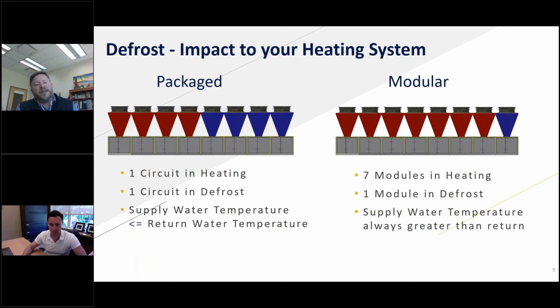And so when we think about that, now, if it were a 4-pipe, so there are air source heat pumps that make 4-pipe systems that can connect to your cooling loop and your heating loop. If your cooling loop is active and there's a cooling load, certainly manufacturers make equipment that can use the cooling loop as its heat source to do defrost. And at that point, all we would really be doing is taking whatever amount of unit that is in defrost, we would take away that capacity, but we wouldn't be actively cooling the loop, because we'd be using the chilled water to actually pull the heat from, okay?